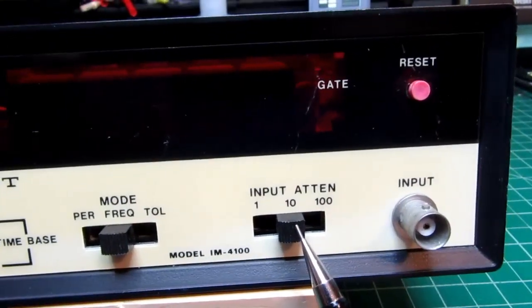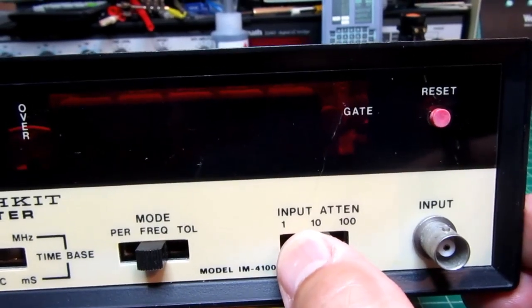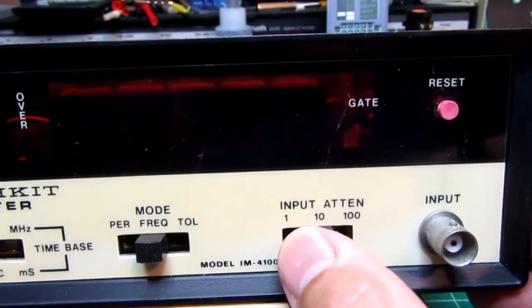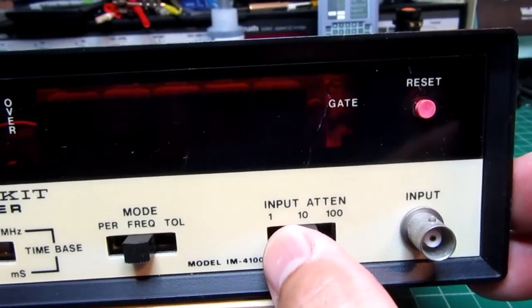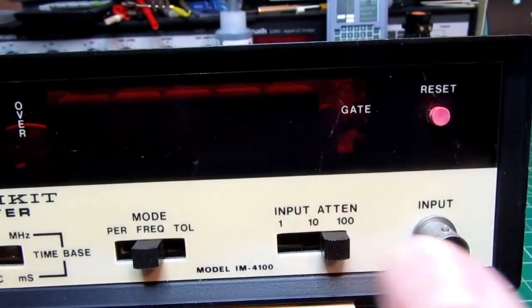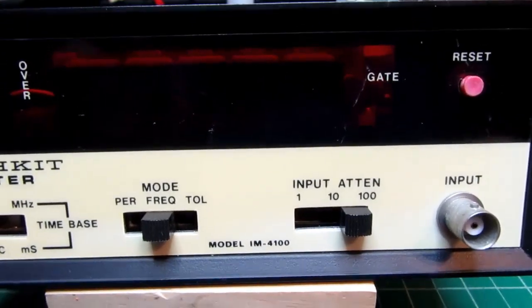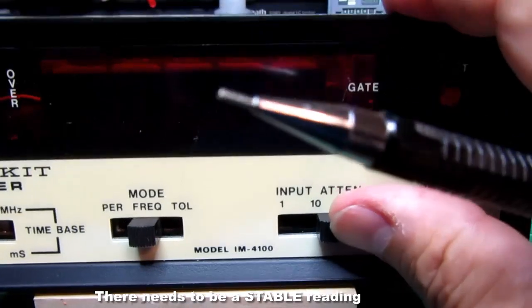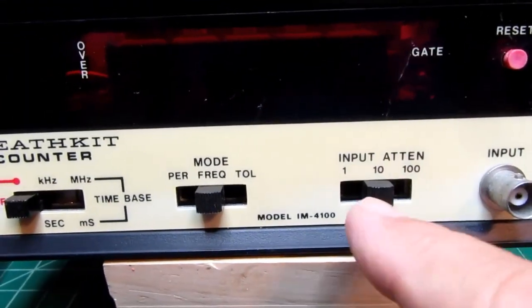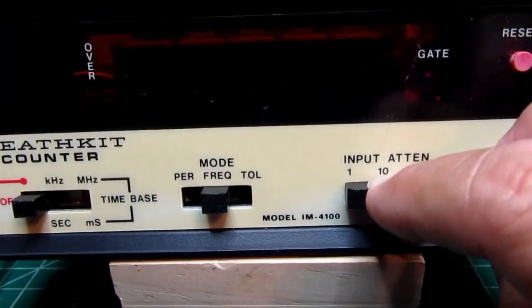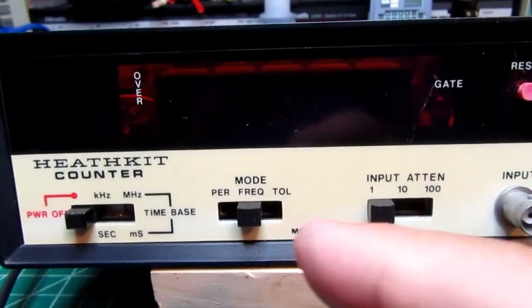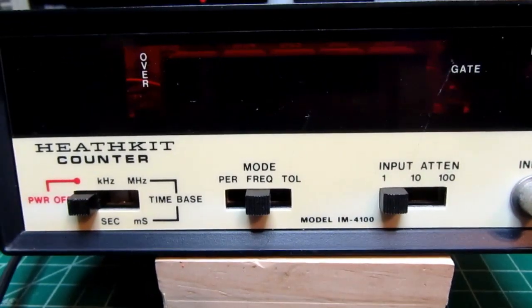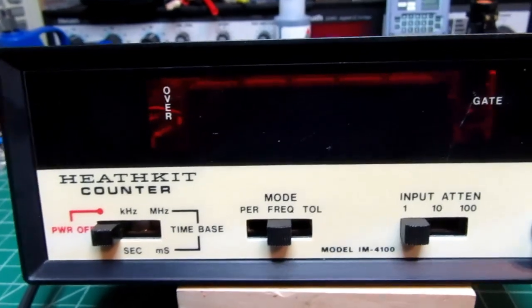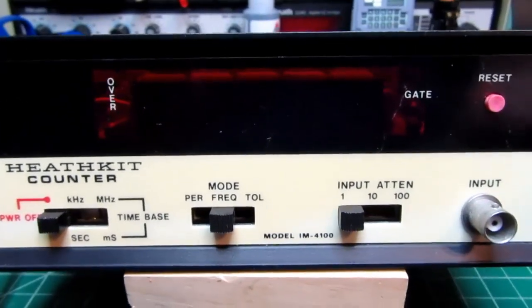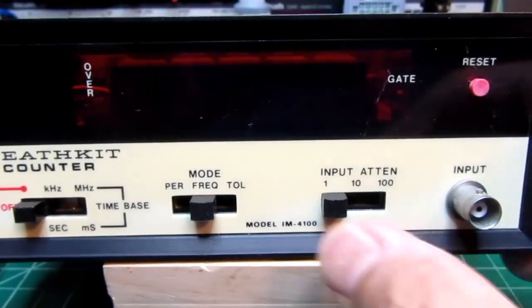And then finally, the input attenuator. Basically, the manual doesn't describe it at all anywhere I could see. You would think you would start out in the 1 and then go up to the higher ones if you've got a higher voltage, but it seems like what you really need to do is start out with it in the most attenuated position and see if you get a reading, and if you don't, then decrease the attenuation until you do. In the demo I do in this video, I started out with it in 1, and instead of a 1 kilohertz display, I was getting like 1.4 kilohertz. Well, if I didn't know any better, I would just assume I'm giving it a 1.4 kilohertz signal, and the counter's telling me the truth. But in fact, I knew it was a 1 kilohertz signal, so I knew to go over here and change the attenuation.